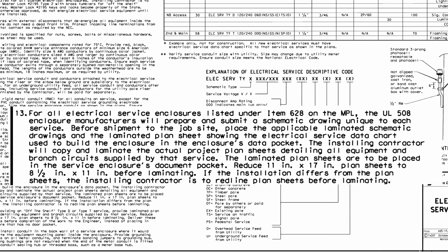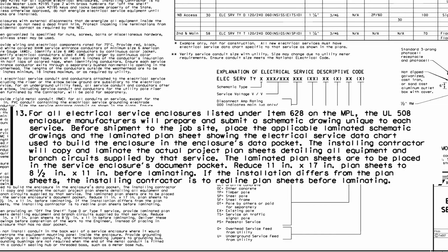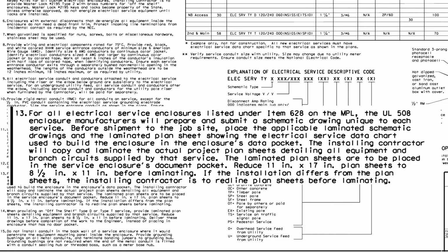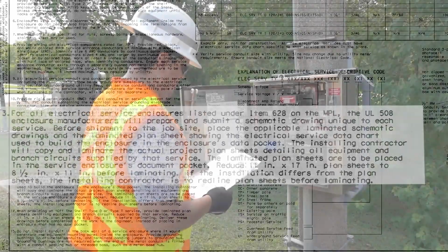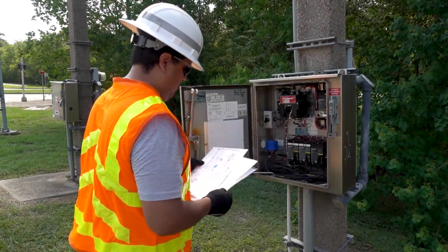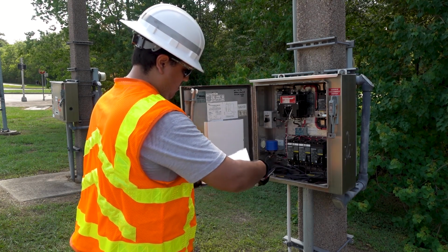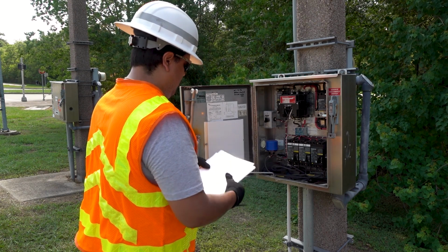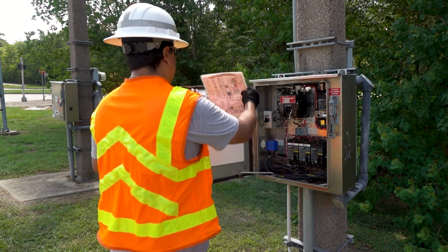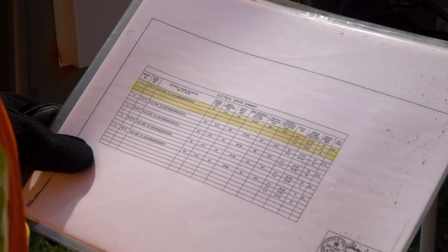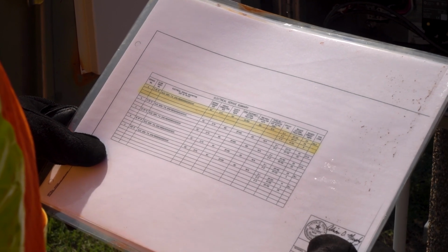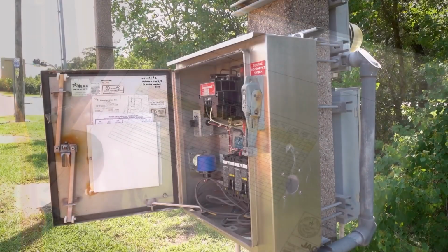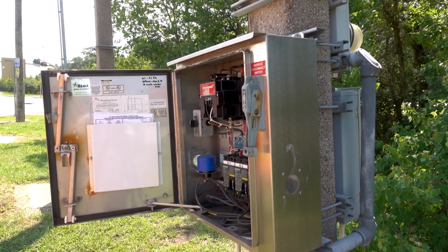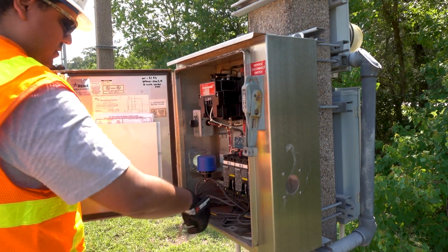ED5 and DMS 11080 also require a laminated plan sheet with the service's electrical service data chart to be placed in the document pocket. The installing contractor will copy and laminate the project plan sheets showing all equipment and circuits supplied by that service. The laminated plan sheets must be reduced to 8.5 by 11 inches to fit in the service documents pocket. If the installation differs from the plan sheets, the installing contractor is to redline plan sheets before laminating. The red-lined plan sheets are to be placed in the document pocket by the installing contractor at the end of the project and should depict all changes made during construction.